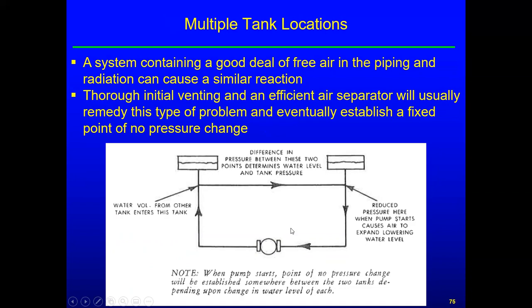A system containing a good deal of free air in the piping and radiation can cause a similar reaction. Okay, so if you just don't evacuate your system, you get enough pockets of air out there. Those pockets of air can act like an additional compression tank, especially if you got a big coil or something that's half full of air. So you could have a significant volume in a big coil. So you can make sure that you vent the system, and get some strange operation from that perspective as well. As well as if you have a coil that's airbound, then obviously it's not gonna work very well.